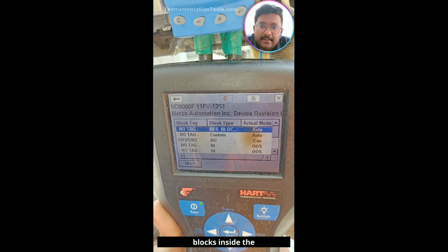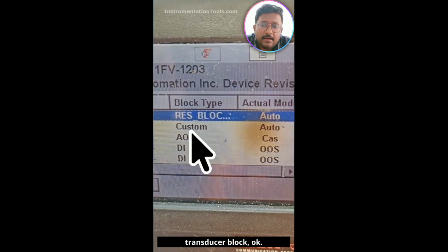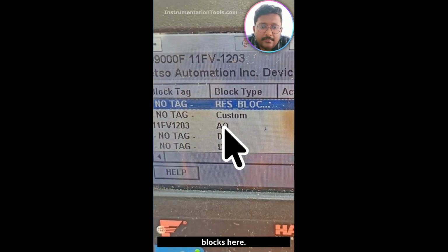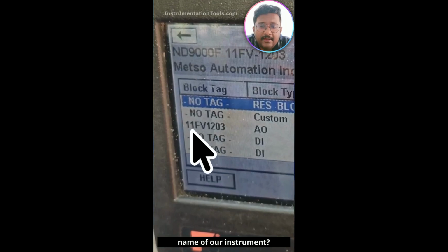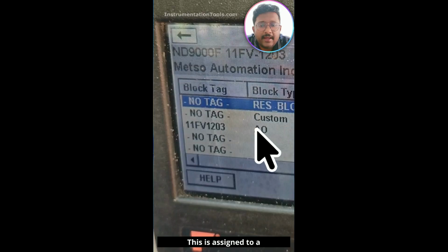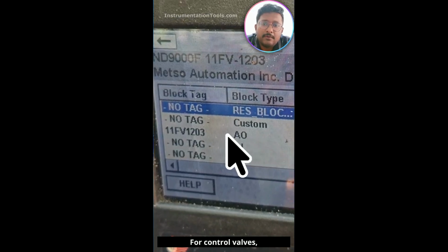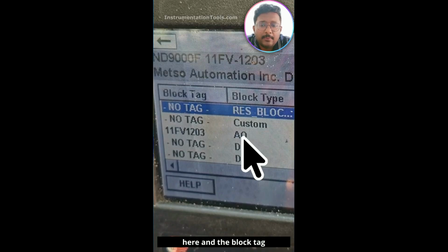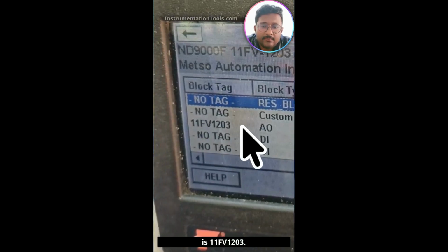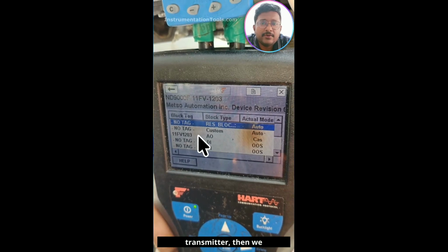So let's see the blocks inside the Foundation Fieldbus parameters. The first one is resource block, transducer block. We will see all the blocks here. What is the tag name of our instrument? 11FV1203. This is assigned to an analog output block. For control valves, it is an analog output. That is why the block type is analog output here, and the block tag is 11FV1203. If it is a flow transmitter, then we will use the analog input block. This only reflects the type of instrument. We are using digital communication between your field device and DCS system.